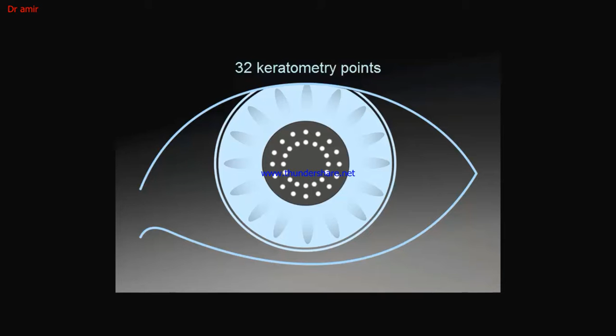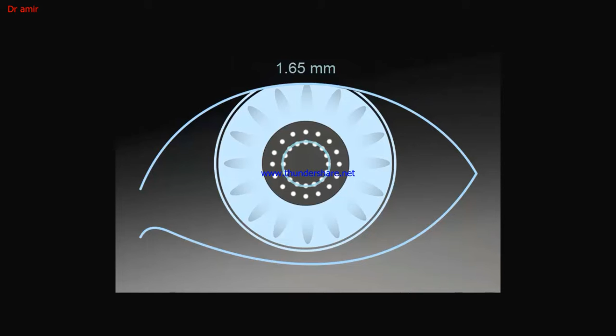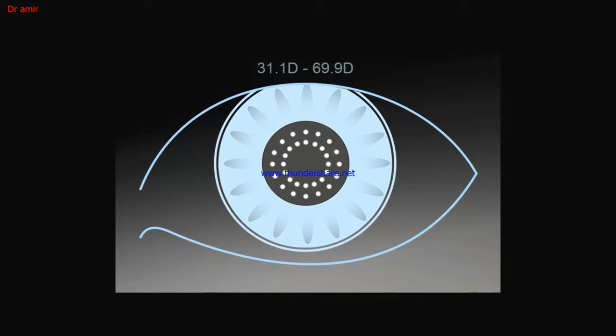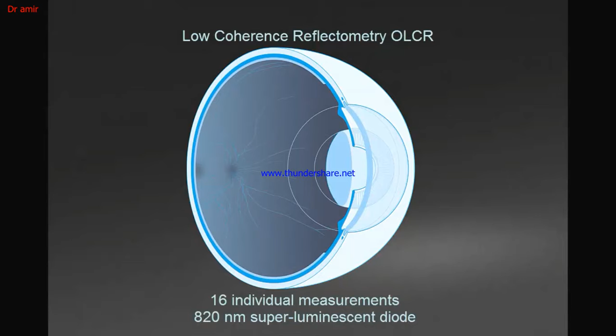Welcome to EyeSuite Biometry. This segment will demonstrate the keratometry features of the EyeSuite software. Lenstar measures 32 keratometry points along 2 concentric zones along the cornea. The inner zone is measured at 1.65 mm and the outer zone at 2.3 mm. Each zone contains 16 distinctive points. The measurement range for keratometry is 31.1 diopters to 69.9 diopters. Keratometry measurements are captured during the biometry acquisition, ensuring that all measurements are on the patient's central visual axis.